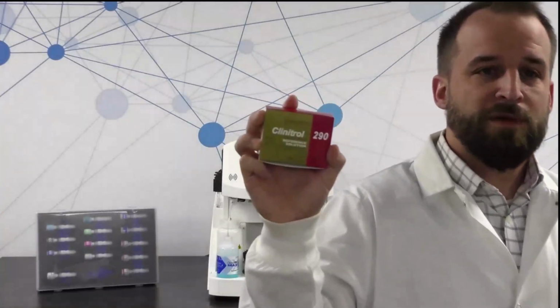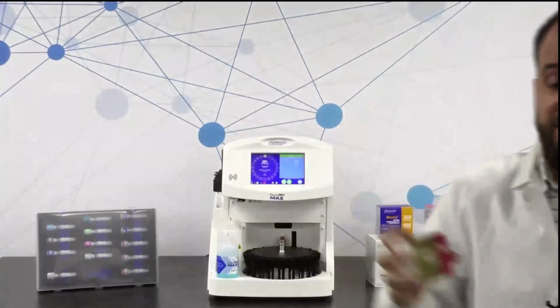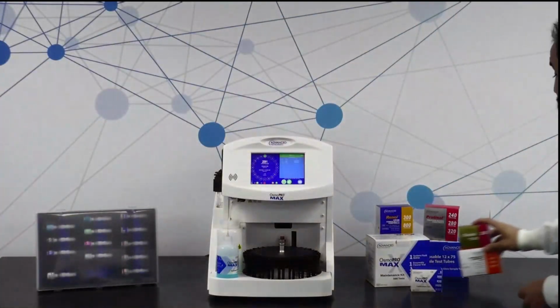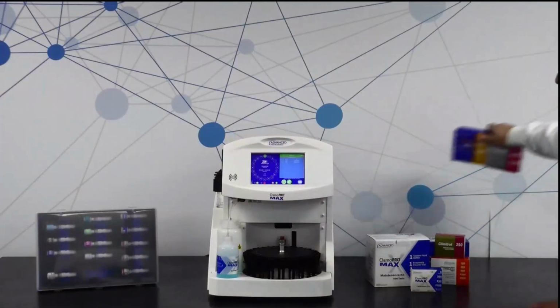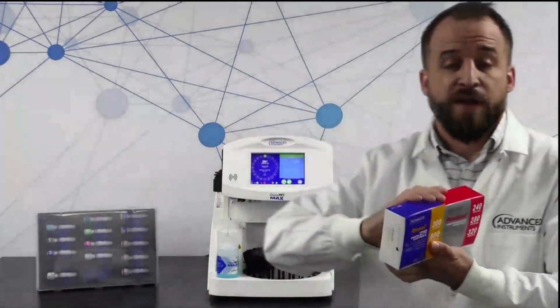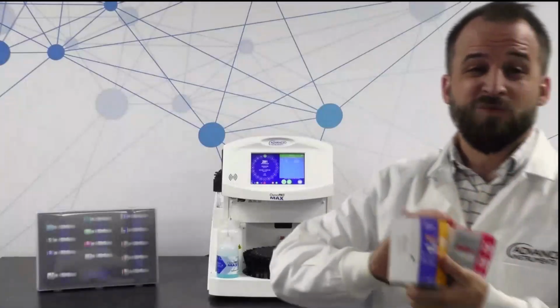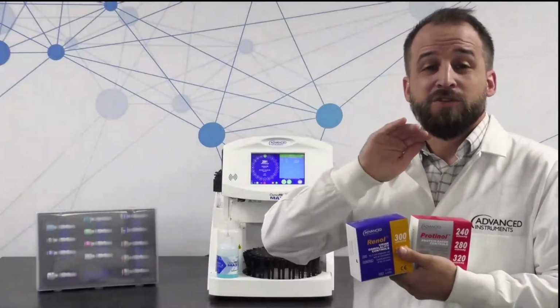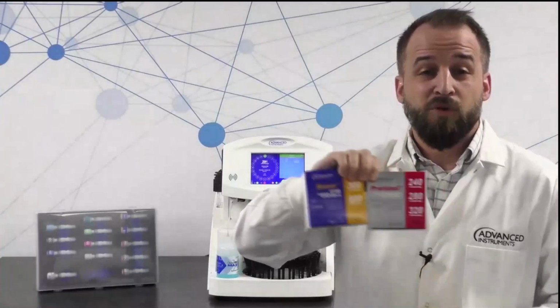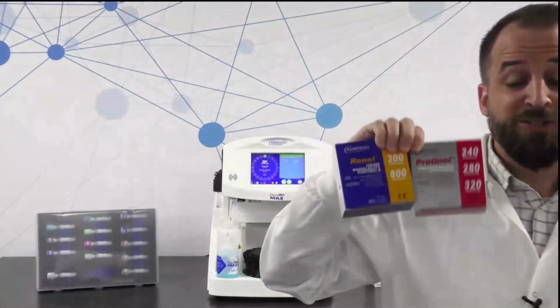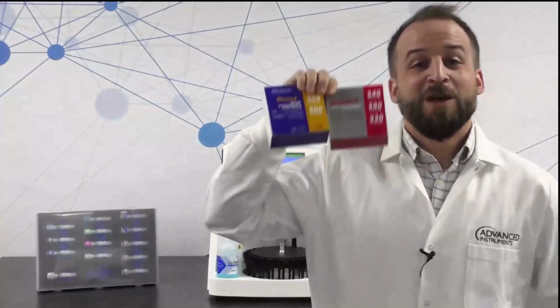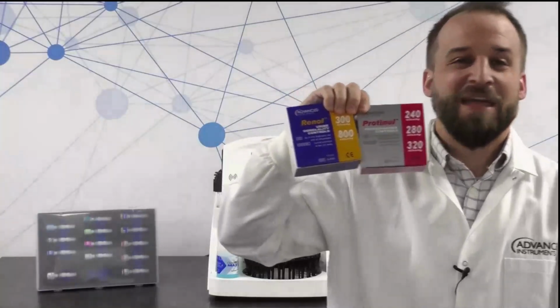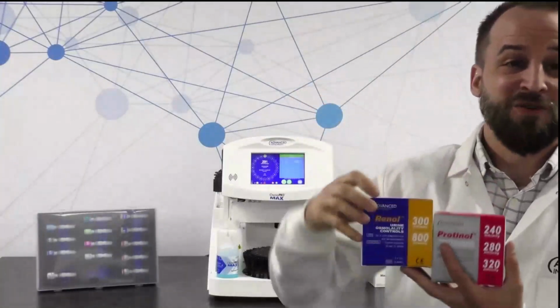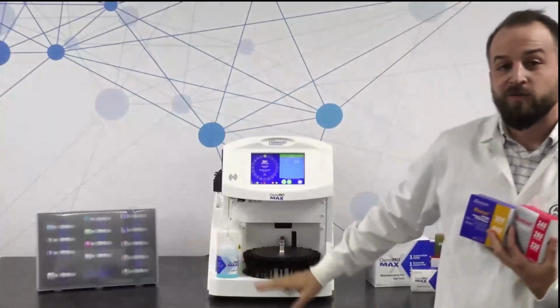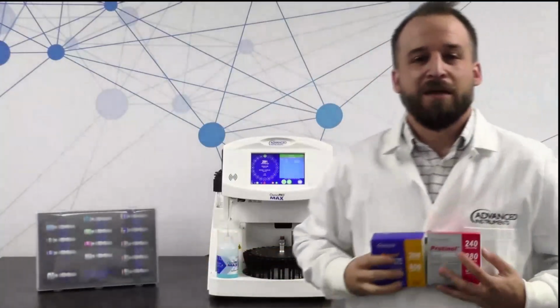So if you have osmometers from Advanced Instruments, you probably do, you're used to running Clinitrol 290. Clinitrol 290 is recommended to run on the instrument every single day. We also recommend, but you are not obligated to, but strongly recommend, these because these ranges are going to be much tighter. They're going to replicate the reportable range that you would actually see in a patient for osmolality results. And they also have compatible ampule adapters to make running these tests really, really easy on board the OsmoPRO MAX.